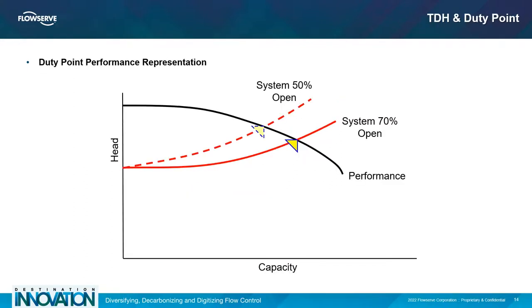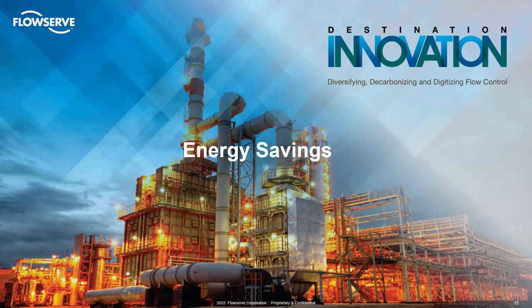Say the pump performance is characterized by the black curve, and the system curve is given in red. If the discharge control valve is throttled to 50% open, then the friction required would increase and the pump would operate farther back on its curve, as represented by the hatched line. If throttling is excessive, there may be a tremendous amount of wasted energy manifesting as damage to the pump and its system.